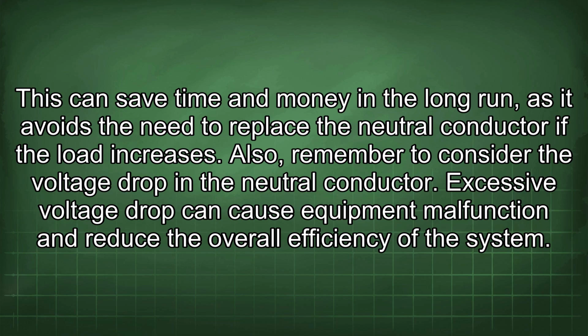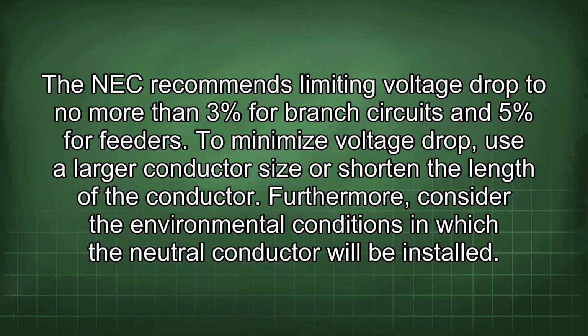Excessive voltage drop can cause equipment malfunction and reduce the overall efficiency of the system. The NEC recommends limiting voltage drop to no more than 3% for branch circuits and 5% for feeders. To minimize voltage drop, use a larger conductor size or shorten the length of the conductor.